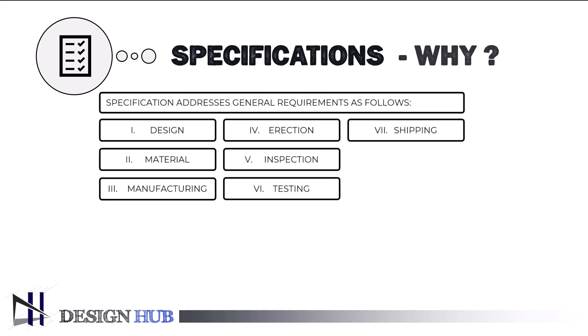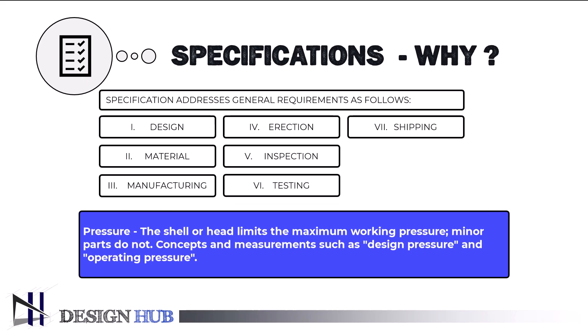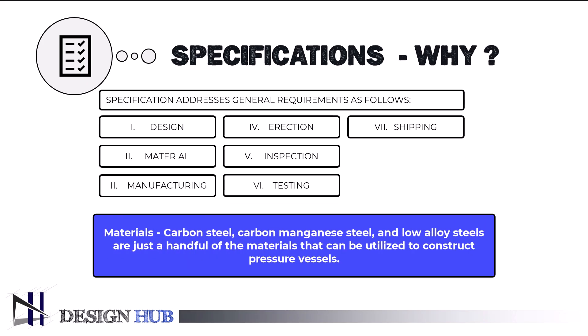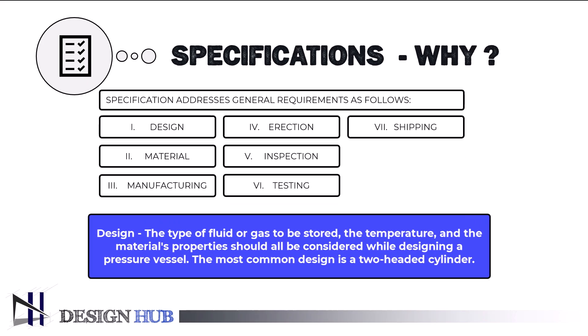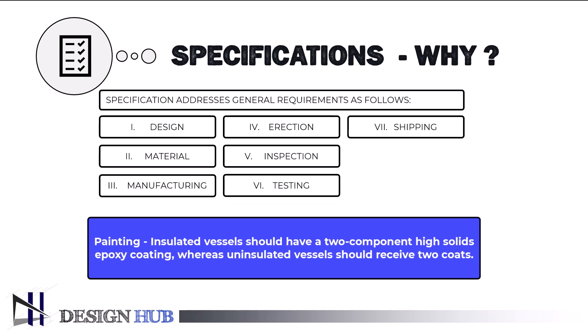Pressure vessel specifications may include the following. Pressure: minor pieces do not limit the highest possible working pressure — the shell or head does. Terms like service pressure and design pressure can be used to describe pressures. Materials: carbon steel, carbon manganese steel, and low alloy steels are just a few of the materials used. Design: a pressure vessel's design should account for the type of fluid or gas, its temperature, and the material's characteristics. The most popular design is a two-headed cylinder. Painting: high solids epoxy coating in two components should be applied to insulated vessels, and two coats to uninsulated vessels.